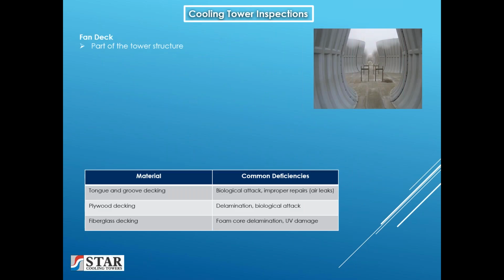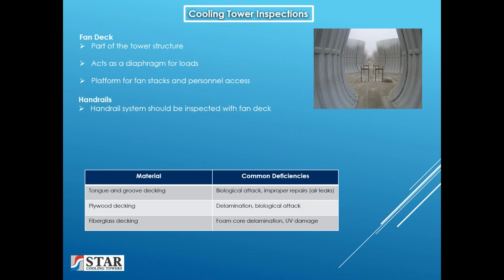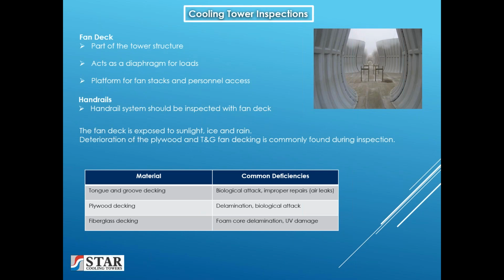The fan deck, as part of the tower structure, acts as a diaphragm for the loads, transmitting dead and live loads to the cooling tower framework. It also provides a platform for the fan stacks and for personnel accessing the mechanical equipment or distribution systems. Handrails should be inspected with the fan deck. Fan deck is exposed to sunlight, ice, and rain. Deterioration of the plywood and T&G fan decking is commonly found during inspection.